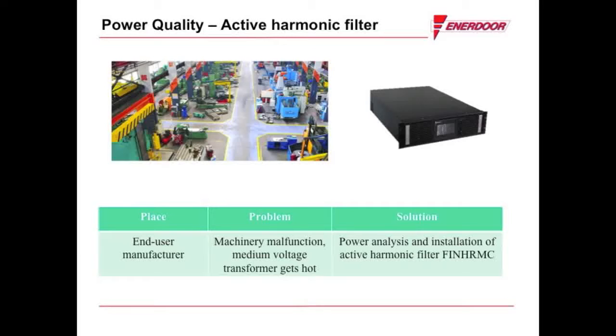Enerdoor made the recommendation of an active harmonic filter. After installation, the customer immediately noticed reliable machine operation, a reduction in audible noise, and a drastic reduction in heat output.